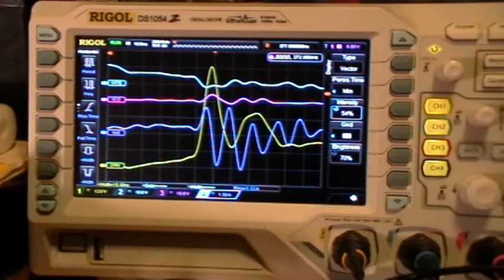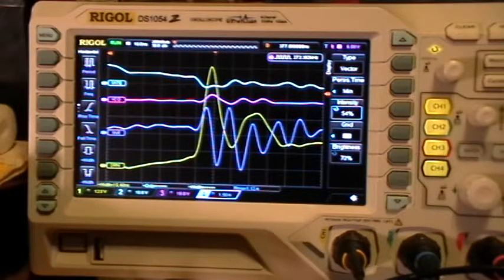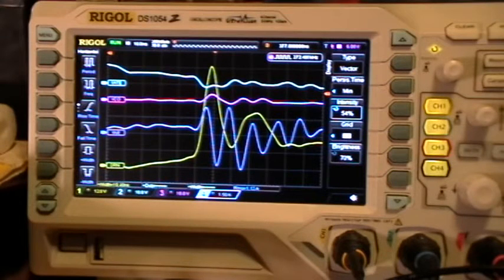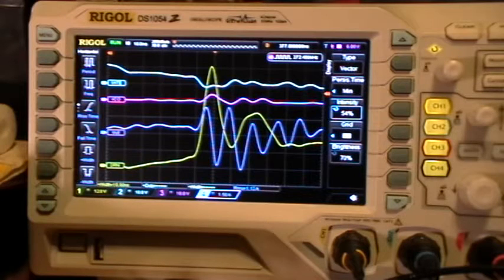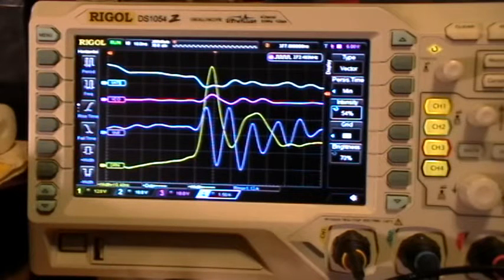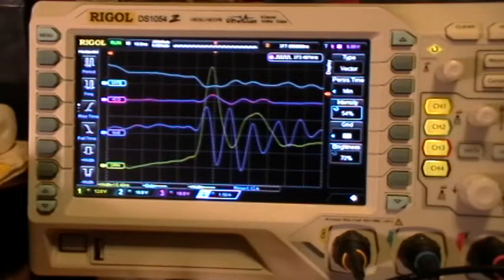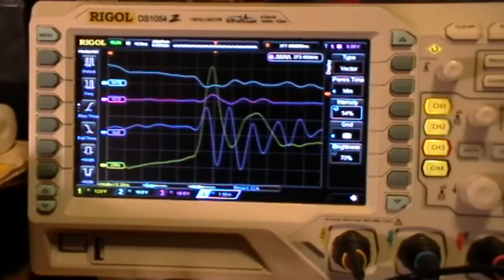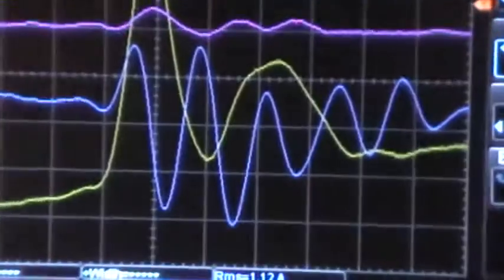Now I'm going to go to the Memory Depth setting. Now at 6 megapoints, you can see that the traces get really nice and thin.